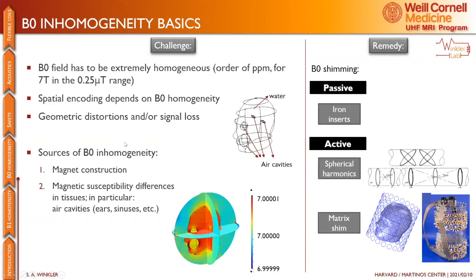The sources for this inhomogeneity are, on one hand, the magnet construction. This is just inherent to the magnet, and it's actually mostly corrected when the magnet is sited. I'll talk about this over here. But what's really more of a problem is the body itself. So air and water have different susceptibility. One is diamagnetic, the other is paramagnetic. And the air cavities in the body cause a lot of problems in that sense, because tissue is mostly water-based, and of course the air would have a different susceptibility.